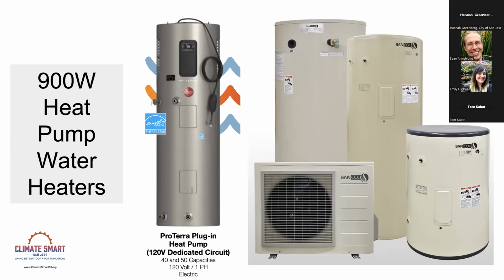This is designed with a special refrigerant, carbon dioxide, that heats water not up to 140, but 150, and then mixes it down to a safe 120. This is what you want.